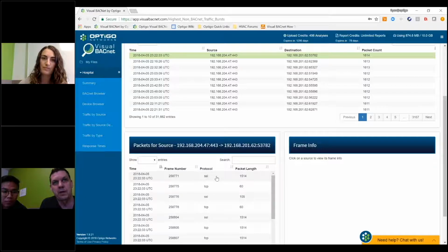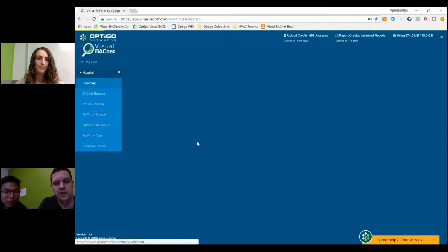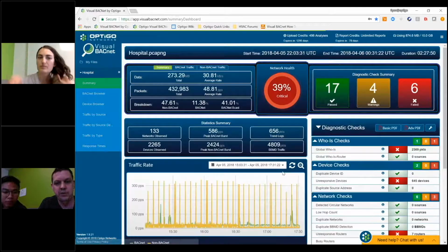But our suspicion would be that the server is doing some standard updates, maybe it's doing time syncs, or it's checking on controllers, or it's checking on the network on a periodic time basis. If it was too much, then you could potentially turn it down or slow it down in the application. But for the most part, it's probably fine. Obviously this part doesn't affect your network, but it does affect how much traffic is coming out of that network pipe. Okay, so that's the first start. If you knew about that and what it's doing, then no big deal.